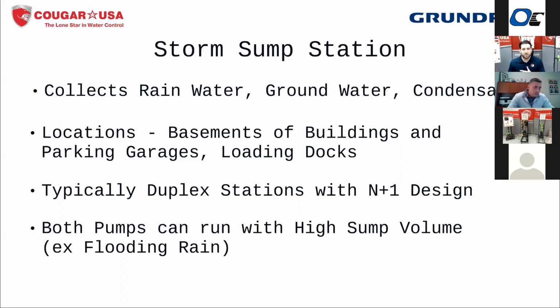Contrast that with a sanitary lift station, we're always going to want one pump to be able to handle the load. So we address that by using a different number of float switches for a storm station versus a sanitary. So a storm station, if we have a duplex, typically we're going to be using a 4 float switch assembly. And we've got some drawings of that later, as well as I can run through the actual sequence of operation there. But really that 4 float switch assembly here is going to allow us to run both pumps without getting an alarm for the high level.